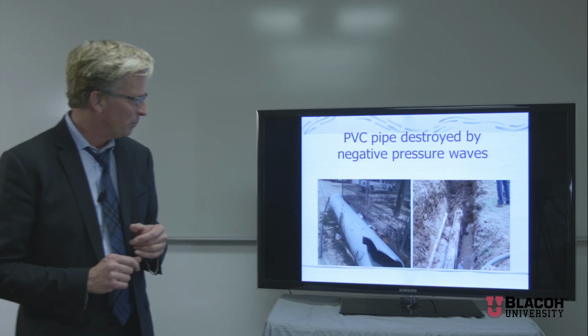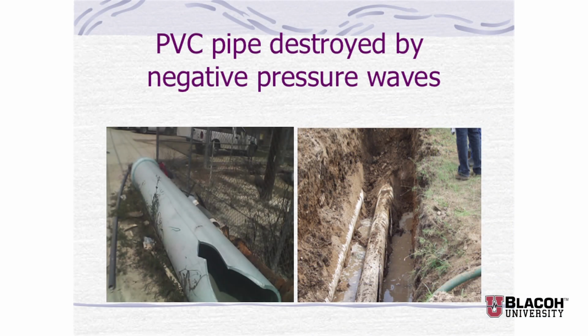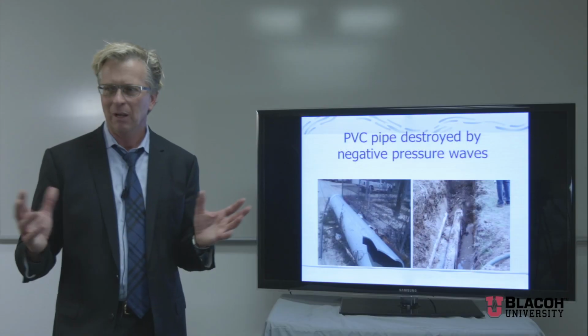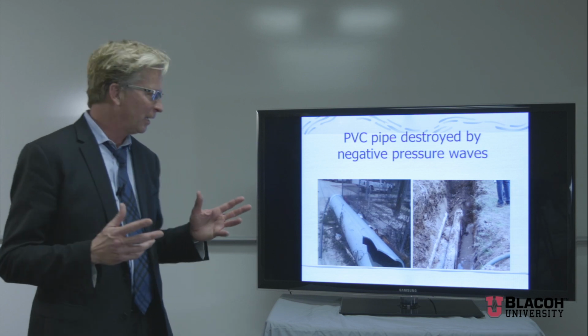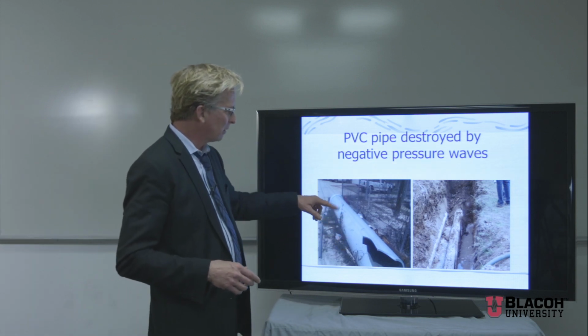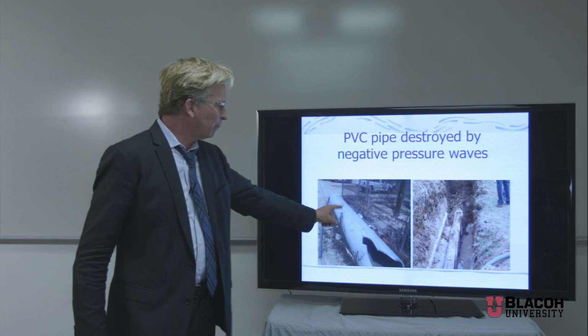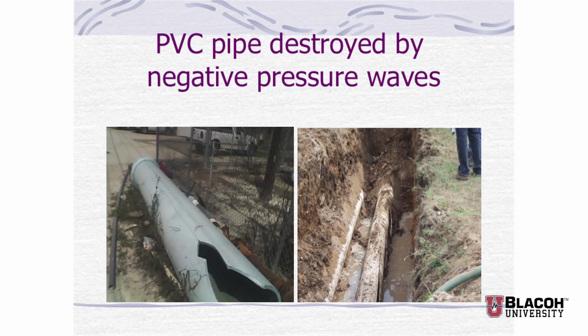So this would be the bottom PVC pipe. PVC pipe, in my opinion, is good to about a -2 psi pressure. Both these pictures depict what happens when you have pressure, vacuum, pressure, vacuum, pressure, vacuum. Typically you get the nice long split across the pipe. In this case, the whole piping is shredded.